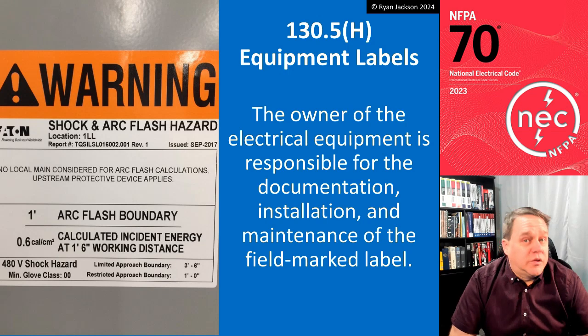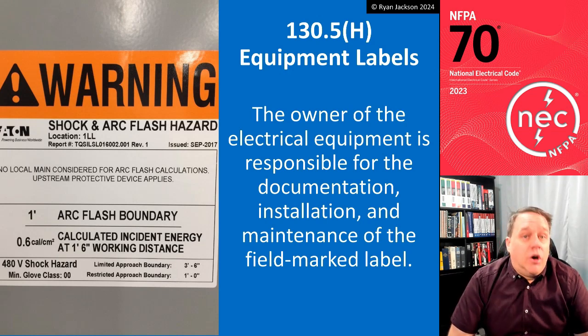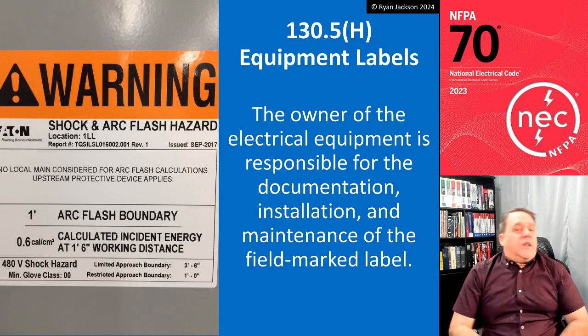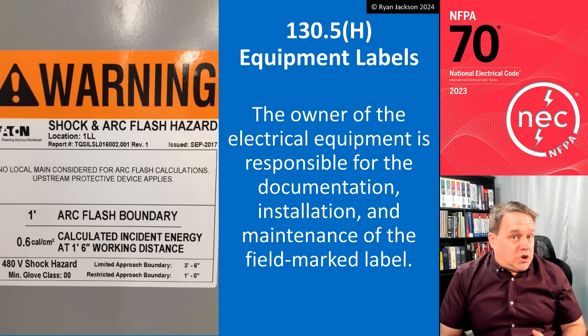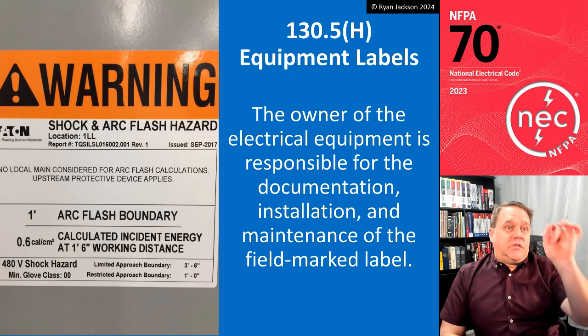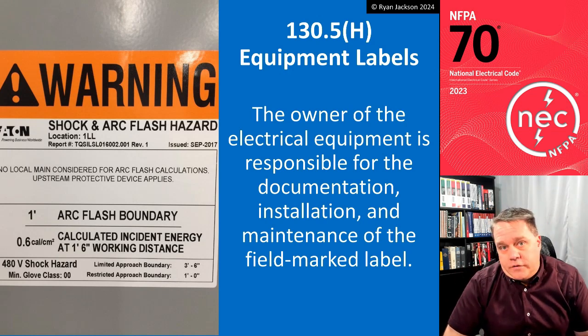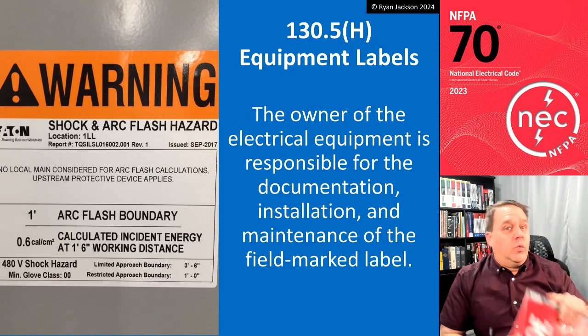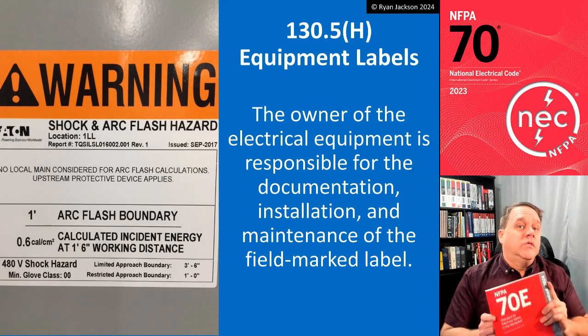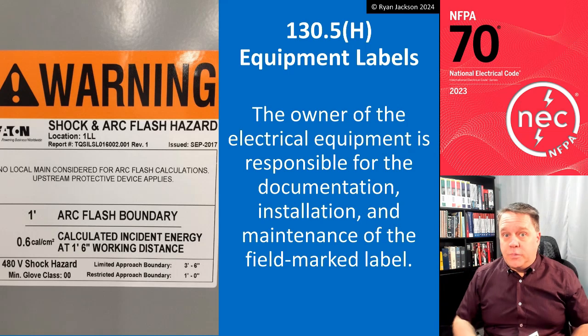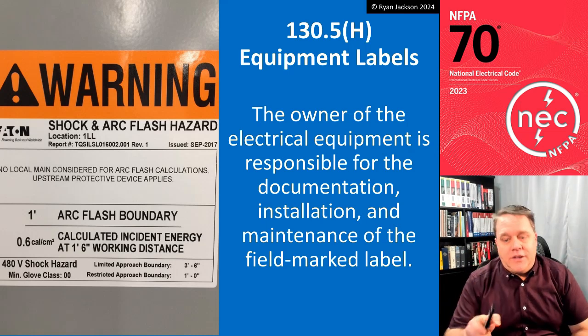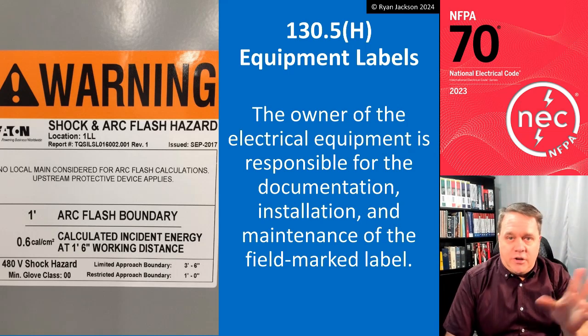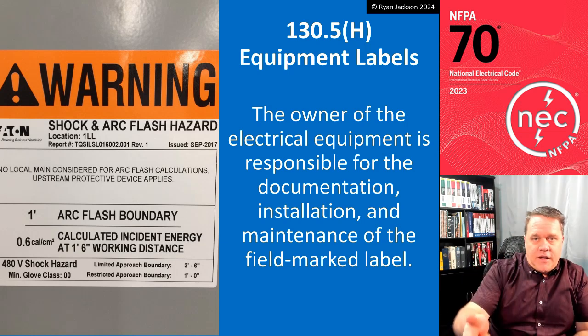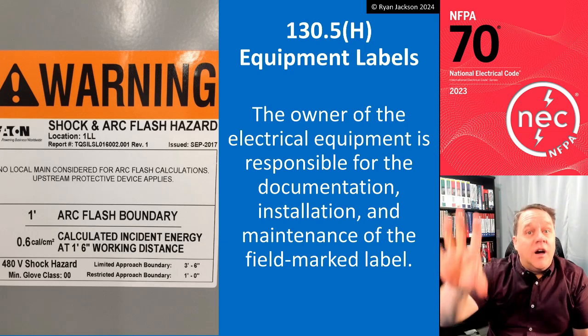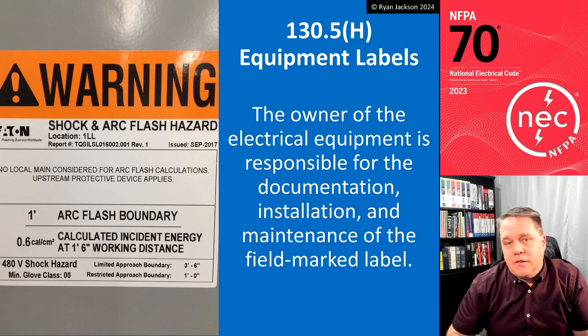All right, so who puts the label on? Well, it's up to the owner of the equipment to make sure that the equipment is labeled. In the National Electrical Code, we cover the installation in the NEC. In the NEC, it just says, hey, put on a sticker that says warning arc flash. In the standard for the workplace, it says whoever owns the equipment, right? Whoever owns the workplace, they have to make sure it has a label that has all of that material on it. The voltage, the arc flash boundary, and one of the options that tell me how to dress.